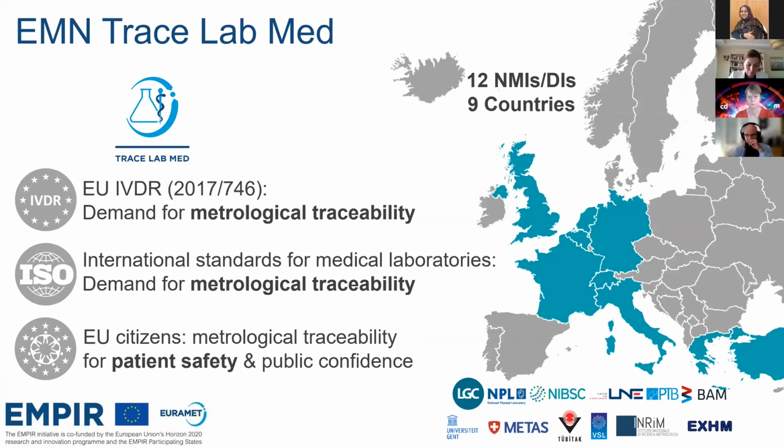So, if you look at the European Union, the comparability of patient measurement results is of such importance that the traceability of calibrators and control materials is a regulatory requirement. And usually European legislation goes hand in hand with harmonized standards that can then be used by stakeholders to achieve legal certainty. So in the field of lab medicine, we have, for instance, the ISO 15189, which specifies requirements for quality and competence in medical laboratories.